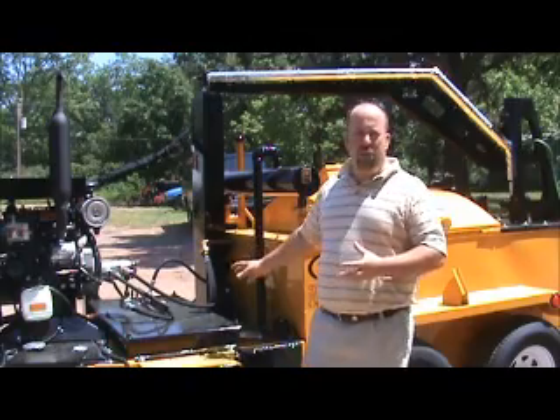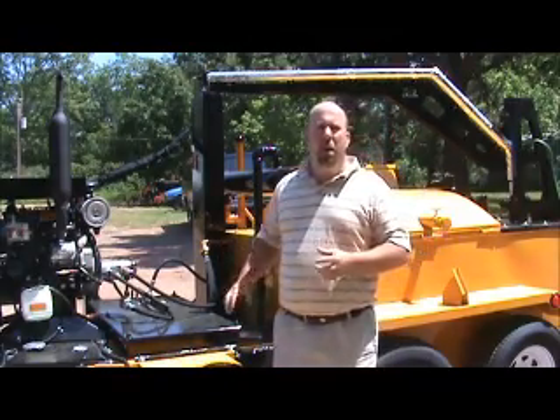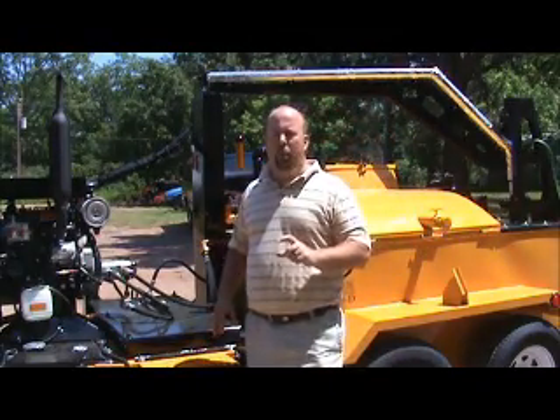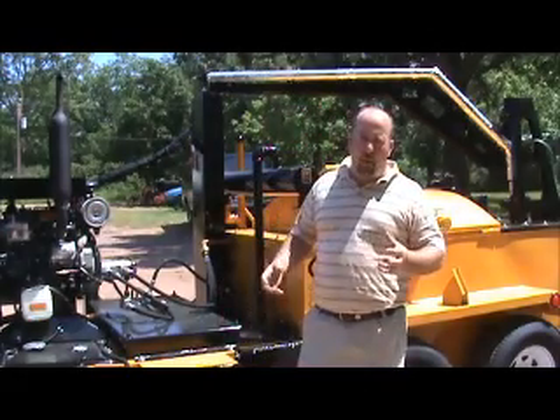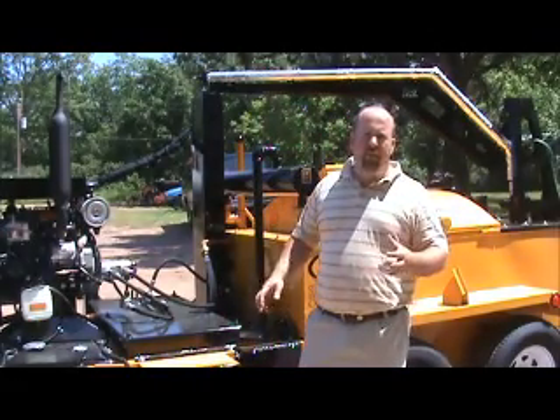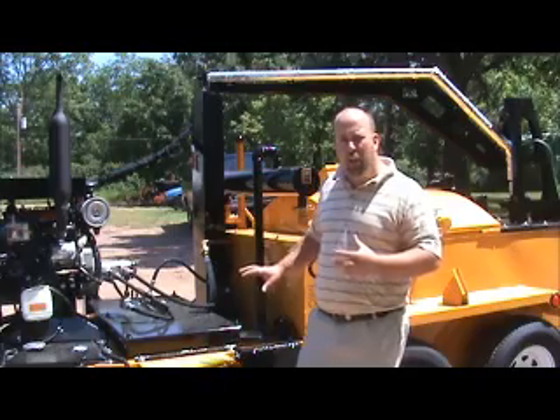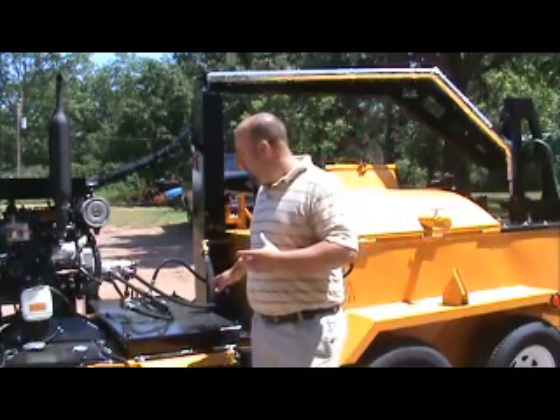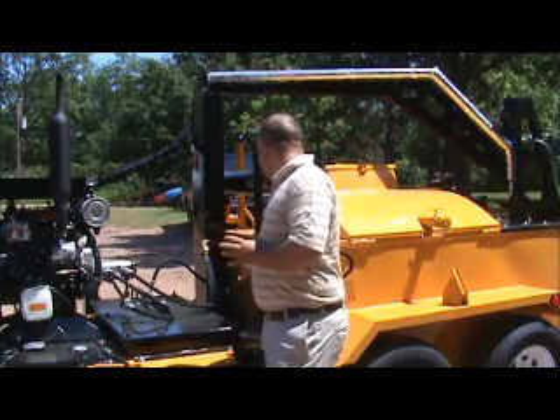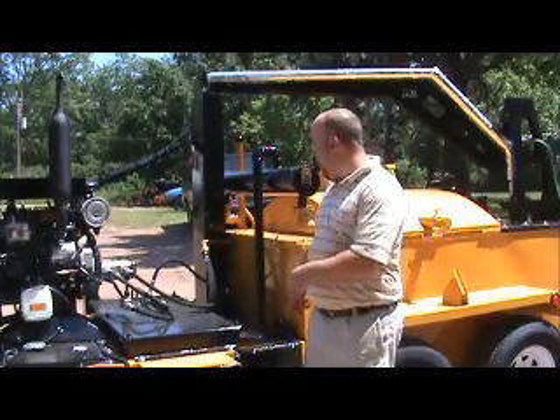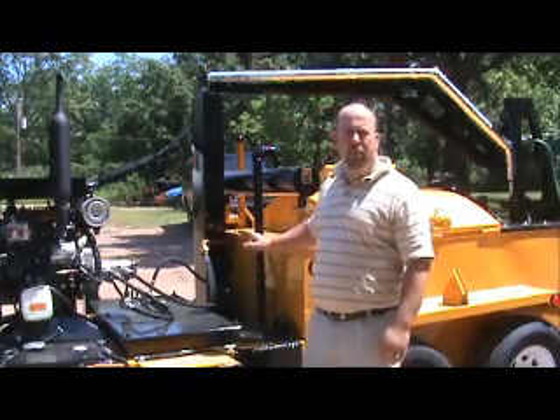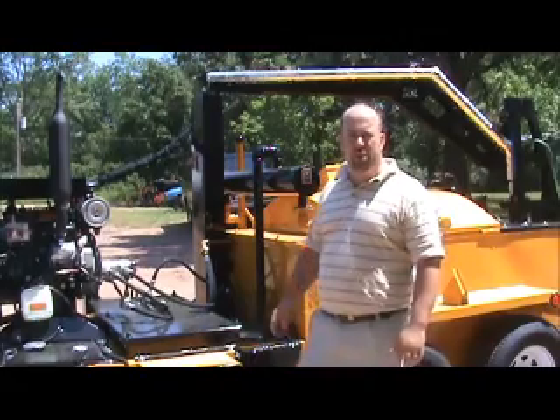At some point you'll eventually have to bring this in to the maintenance shop, and they'll have to put new packing rings in the pump. Again, you're going to get probably 500 to 700 hours of life out of that packing, so it's a maintenance item. When we start the engine, we're going to walk around and make sure that the pump is turning. Once the pump is turning, then we're going to go start our burner system.